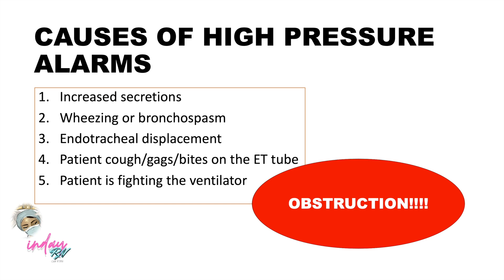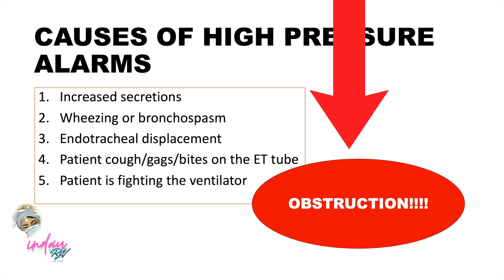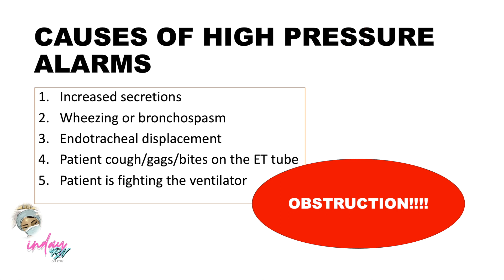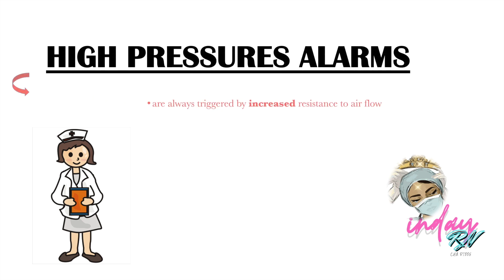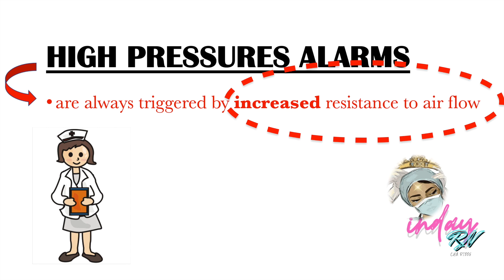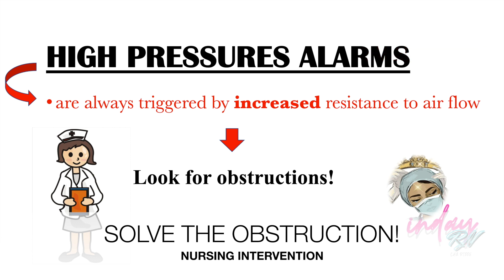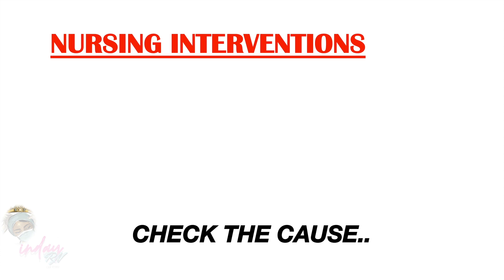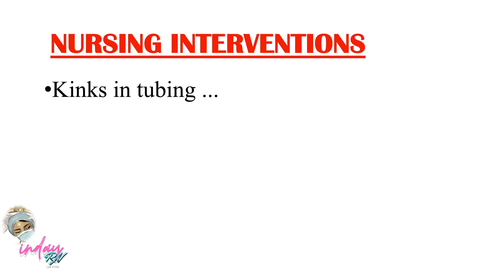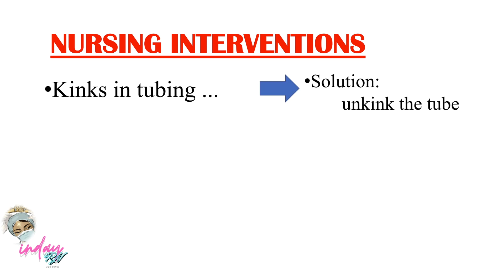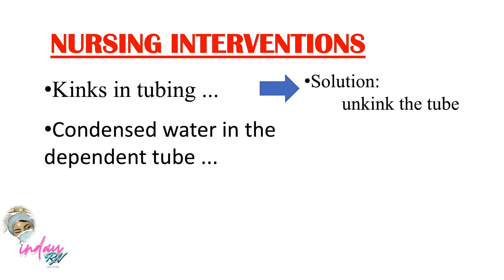In high pressure alarms, all causes result in obstruction — obstruction in the ET tube or the patient's airway. High pressure alarms are always triggered by increased resistance to airflow. Our nursing interventions: first, check the root cause of the obstruction. If there is kinked tubing, unkink the tube. If there is condensed water in the dependent tubing, remove it or empty the tube.